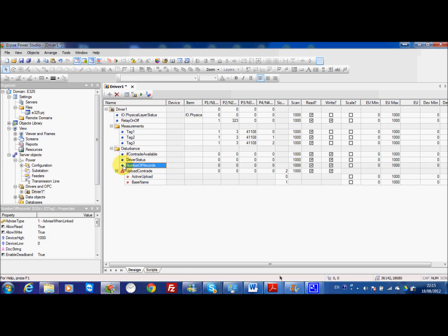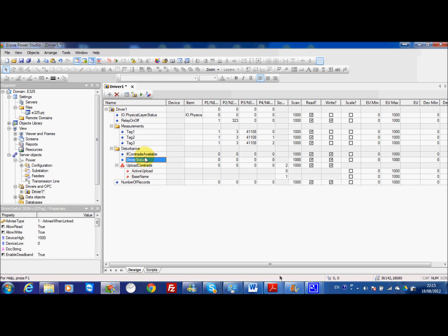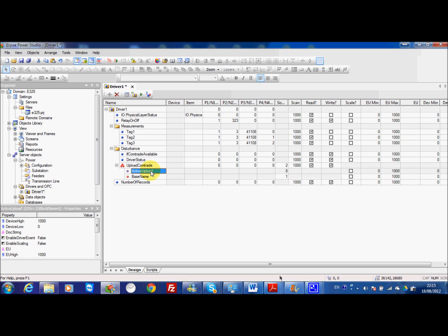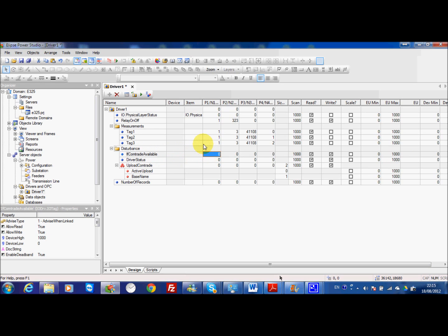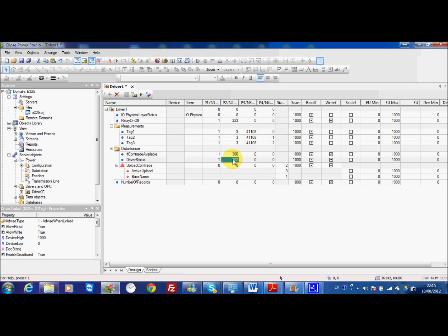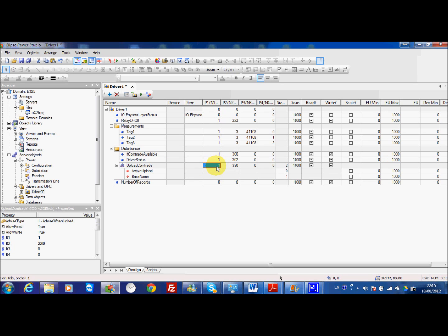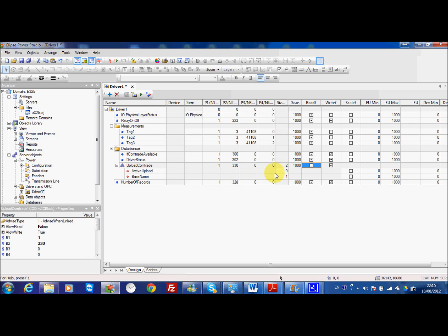This one number of records is not so necessary but the first and second one and the block, this is what you need to upload the comtrade. If comtrade available, this tag the code is 300. Second one driver status is 302. Then the block for the upload comtrade is 330 and the last tag which is less important is 328. This one is only read only.